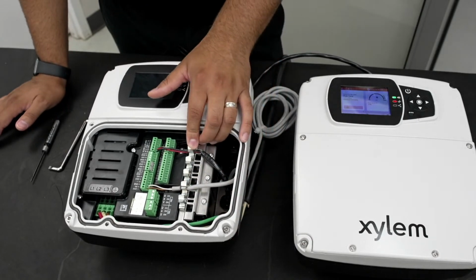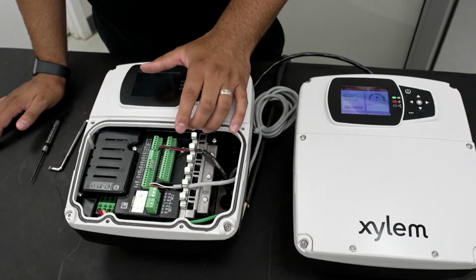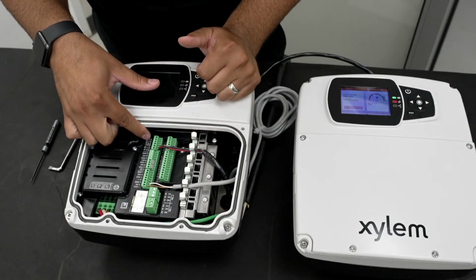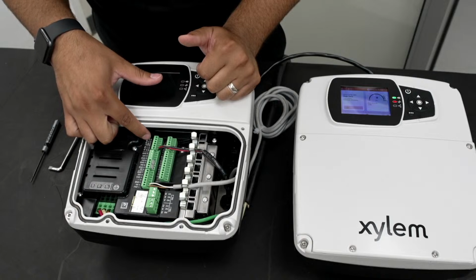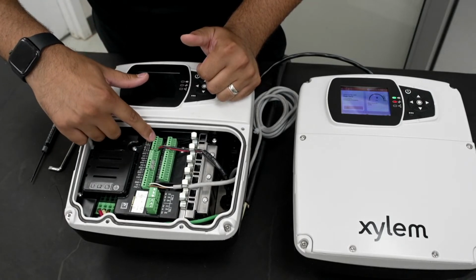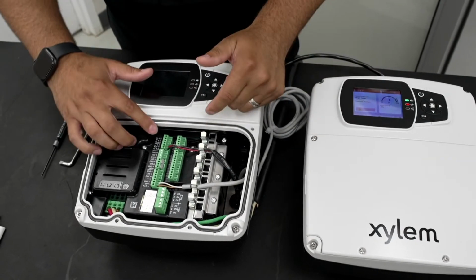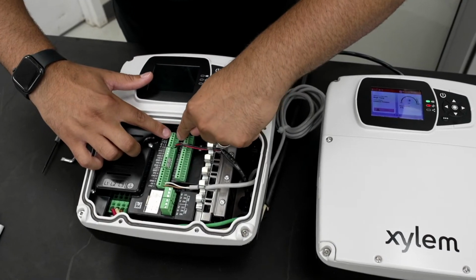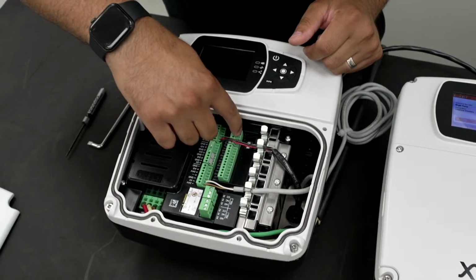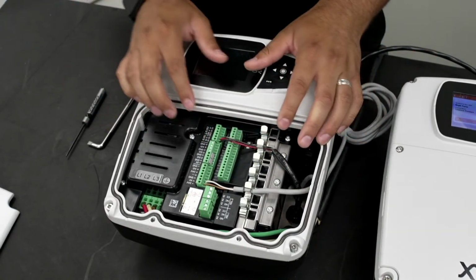A couple perks with our communication wiring is we have plenty of RS-485 ports. So we have a bank set for BMS or SCADA systems. You can see 31, 32, 33 here, and you got some ports here. Each VFD has to be daisy chained together. So instead of cramming 2 sets of wires into the same terminals and going to the next one, we basically have an input and output going. So there's just plenty of room and strips there for communication.